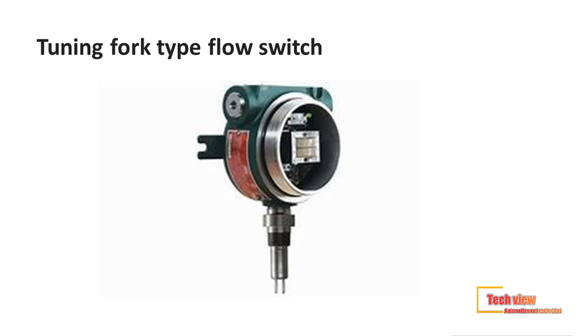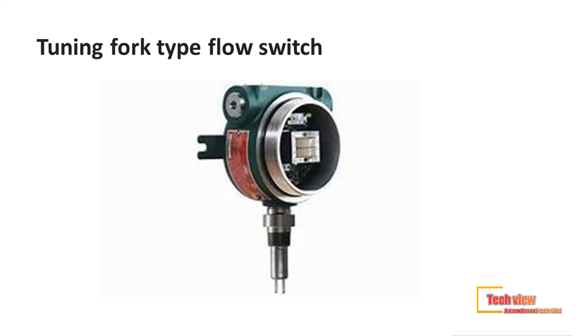The next type is the tuning fork flow switch. The vibrating fork type working principle is simple and effective. These flow switches are reliable, cost-effective, and very popular for use in detecting the presence or absence of liquids and bulk solid materials. The working principle is based upon detecting the change in harmonic vibration frequency of the sensing element as a result of the presence of the target media.